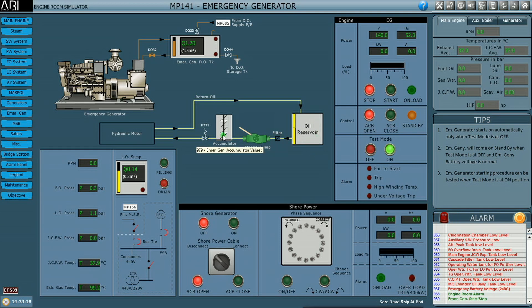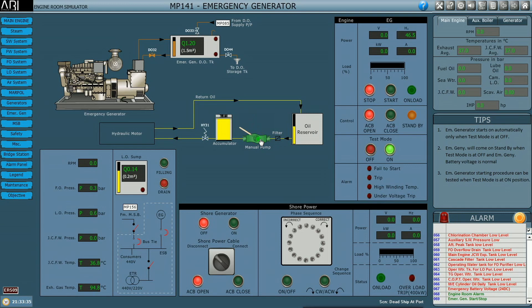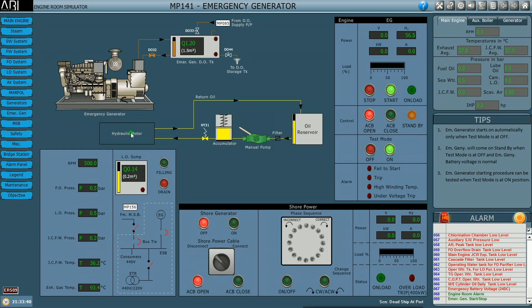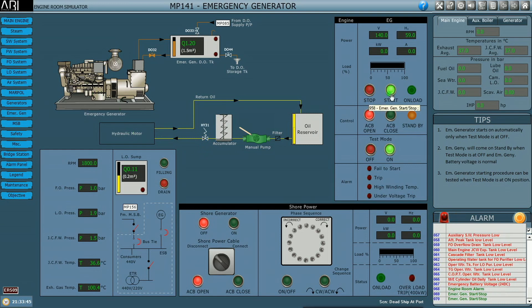Using the manual hand pump I'm going to pressurize the accumulator with hydraulic oil, and after that I'm going to release this pressure to the hydraulic motor which is coupled with the crankshaft. You can see it has cranked the engine and the engine has picked up on fuel. Once the engine picks up on fuel, the hydraulic motor gets disengaged from the crankshaft and it will be running on fuel. This is just a starting mechanism for the generator engine.